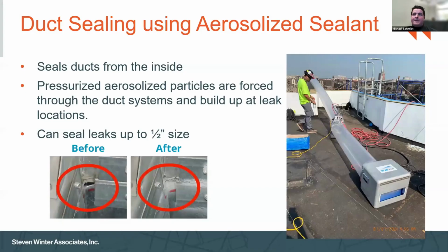Kelly again. So historically, our firm has addressed duct leakage and duct sealing using this aerosolized approach. AeroSeal is a product that's been on the market for some years now, and it can be a very effective way to seal the ductwork. Now, this is only sealing the ductwork. We mentioned a few of the other areas you can have leakage within the equipment or within the accessories. This only seals ductwork, but it can be very effective. Essentially, that entire duct system is capped off and pressurized. Sealant particles are misted into the duct system, and they build up at all the leakage locations.